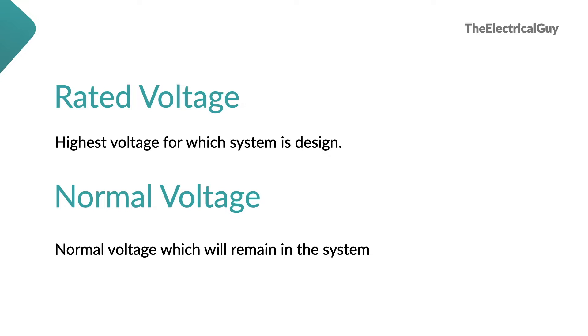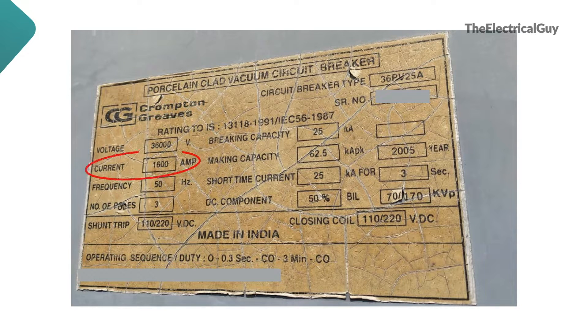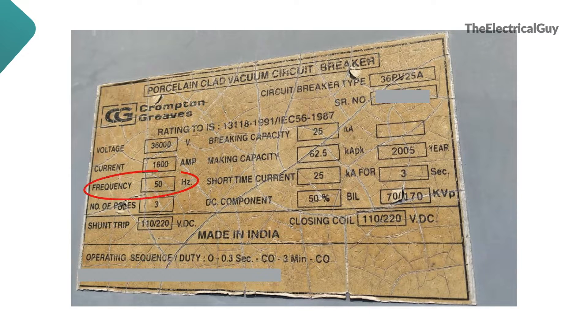Similarly, for the 245 kV voltage level, rated voltage is 245 kV and the normal voltage is 220 kV. Next is rated current — this is the rated current for which the circuit breaker is designed. The circuit breaker is able to carry 1600 A without any problem.